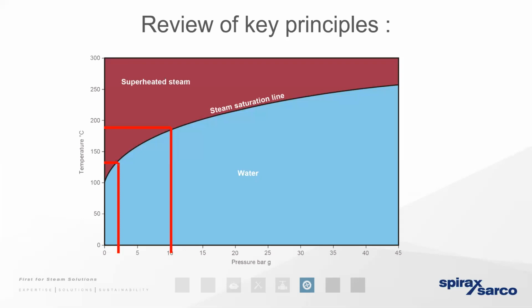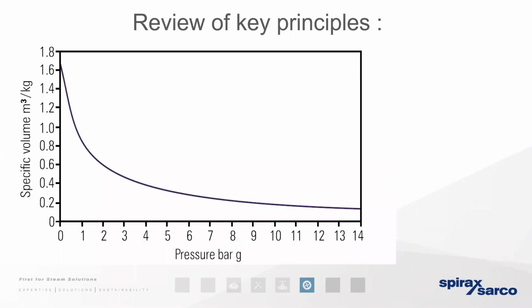Now, the flash steam is a change. It's not just a change of phase from a liquid to a gas. It's a change of energy. It's a change of energy from sensible heat back to total heat, meaning that there's just as much heat energy in flash steam as there is in plant steam. We either need to reduce and control the production of flash steam, or we need to find a way to recover it in some way.